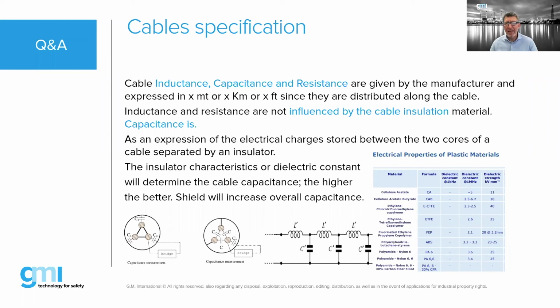If I remember correctly, PVC was not a very good insulation. The other ones were better cable. Of course, also shield. Well, a shield is used, as earlier Bob discussed, to provide separation for IS security. It also introduces more capacitance, because now you have another core, which is the shield.